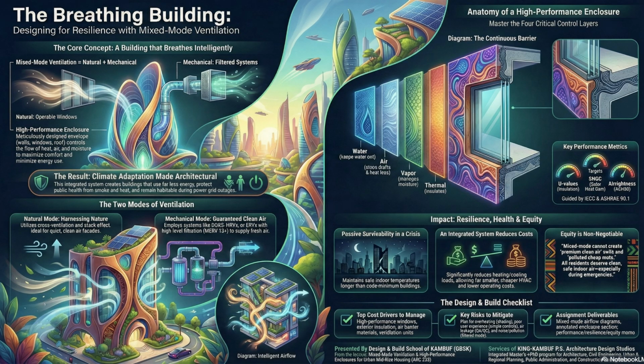And the building codes set a minimum. Right. Codes like the IECC or ASHRAE 90.1 set minimum U values for walls and windows. High-performance design always aims to be significantly better, meaning lower than that minimum. And especially in a glassy urban building, you have to worry about the sun. So that means tracking the SHGC, the solar heat gain coefficient. The SHGC is absolutely crucial. It's the fraction of solar radiation that actually passes through the glass.